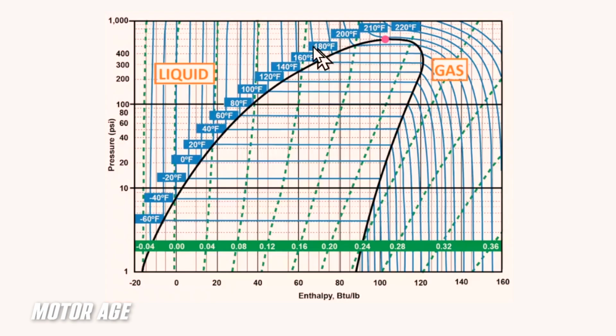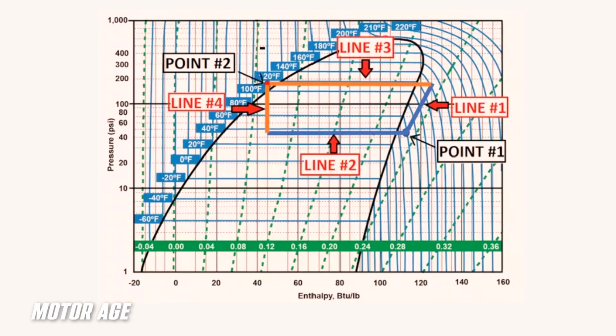The significance is this chart is showing refrigerant changing from a liquid to a gas. And as we talked about at the beginning of this video, liquid refrigerant increasing in sensible heat is what's happening here. Once the liquid refrigerant reaches a certain temperature and begins to boil, as it changes state, sensible heat temperature remains exactly the same. And as soon as we become a fully saturated gas, temperature of the gas will begin to increase again in this superheat region right here. And on the flip side, temperature will begin to decrease in the subcooling region right here. So we are going to be able to plot information that will give us this geometric shape here to show us visibly thermodynamics occurring within the refrigerant loop.